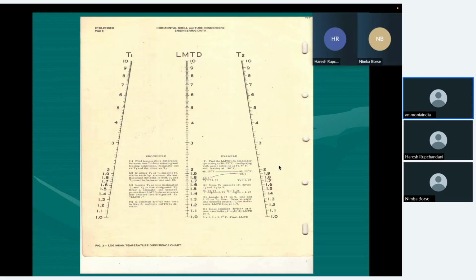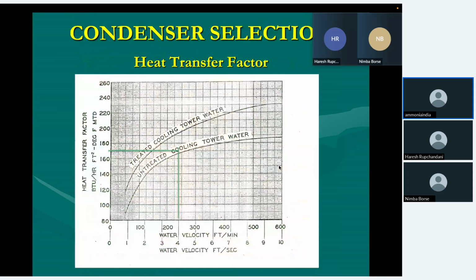So this is an indication for quick selection of LMTD. You can calculate it also, or use T1, T2 and join a line. The center line will give you the LMTD. Now we are calculating the heat transfer coefficient. We have seen water velocity is 250 FPM. If you take a straight line from 250 FPM upwards, and let us assume we have not treated the cooling tower water, we intersect this line at a particular point on the line below, and then go horizontally towards heat transfer coefficient. You will find the heat transfer coefficient is around 165 BTU per hour per square foot.